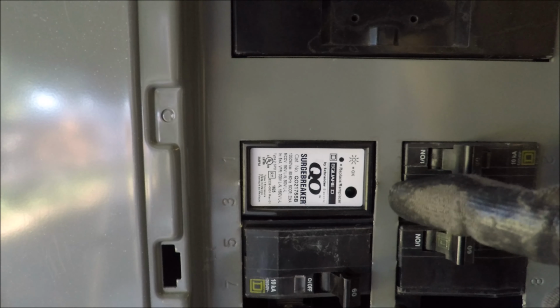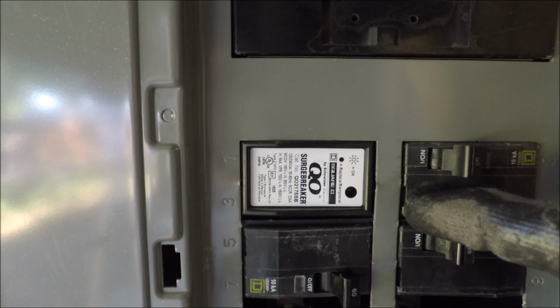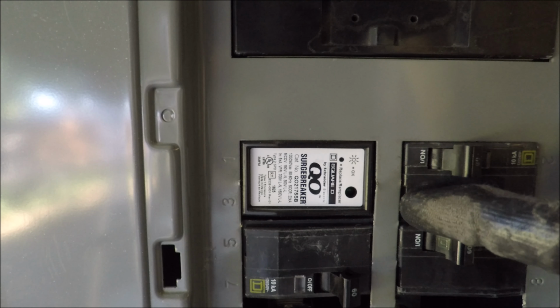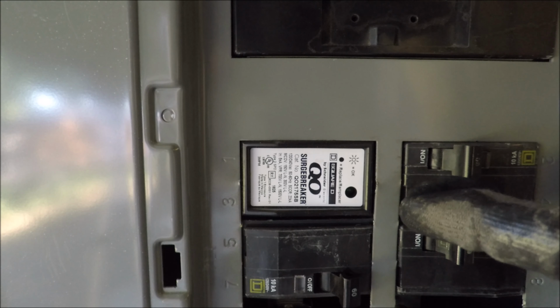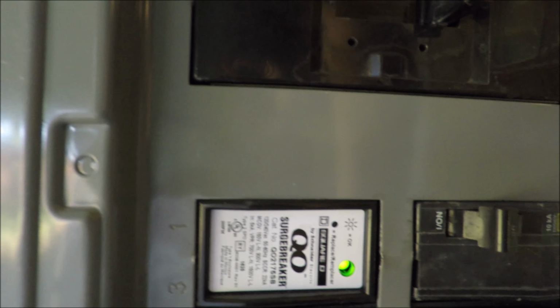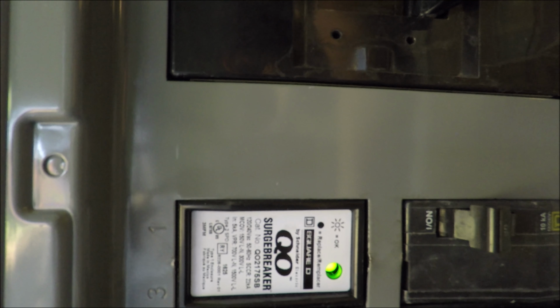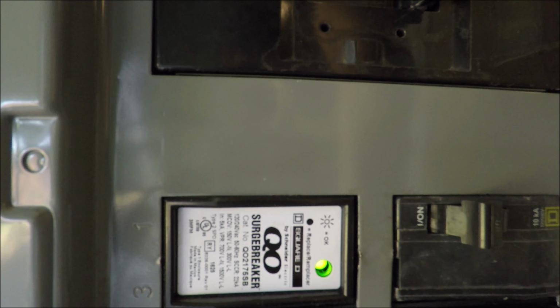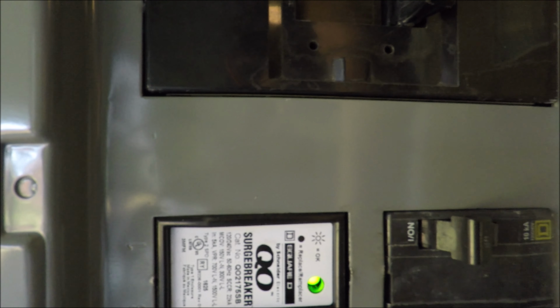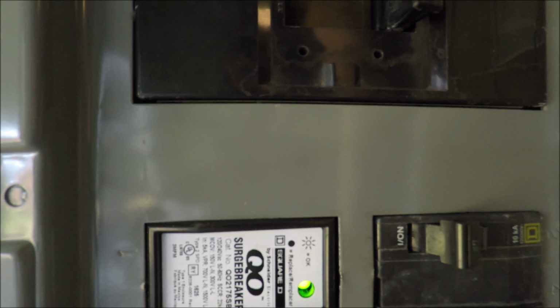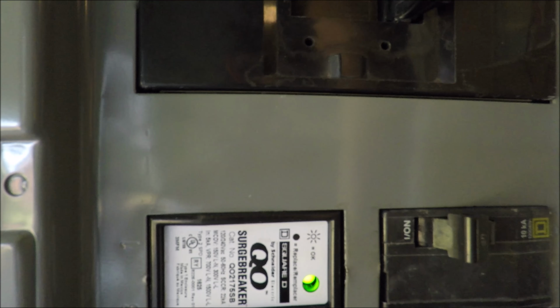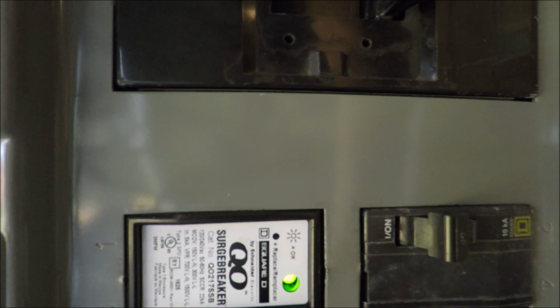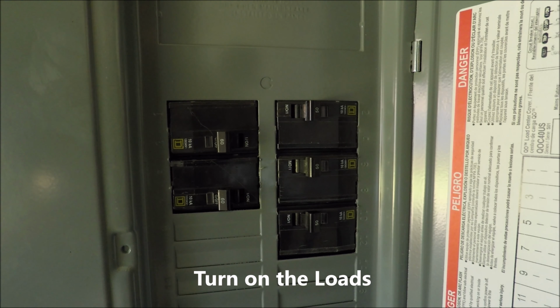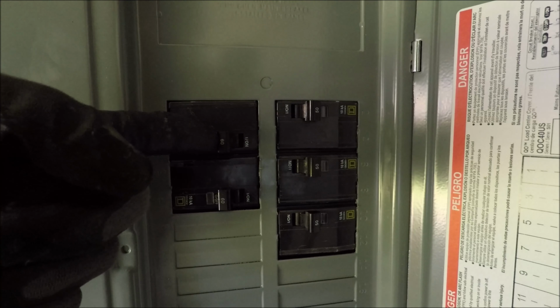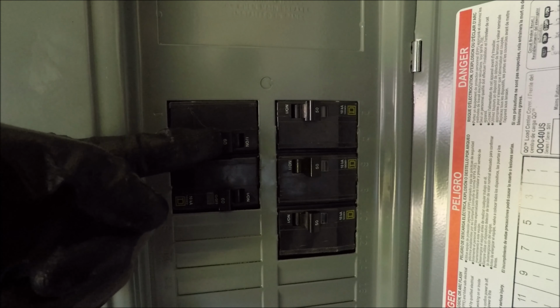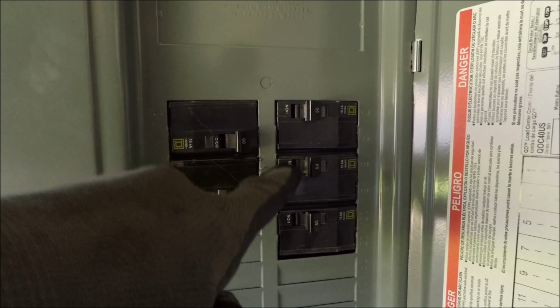They will help to protect your inverter, which could cost thousands of dollars, from lightning strikes and surges through the municipal utility connection. When power is supplied to the panel, you'll see a light indicator come on the surge protection device in the panel, indicating that the panel is protected. On most of these devices, if that LED light is flashing, the surge protection device needs to be replaced. The last step is to turn on the loads for your inverter. This breaker protects the load side of my inverter. These breakers are for the loads.